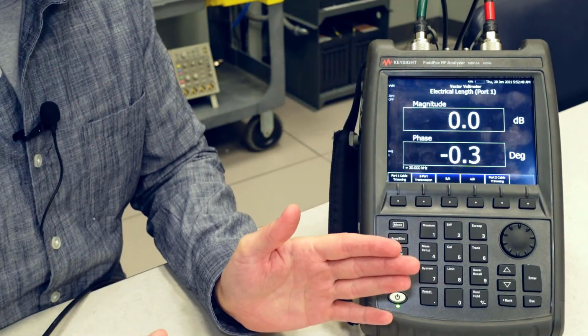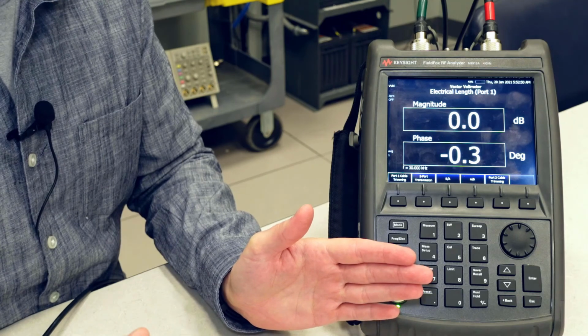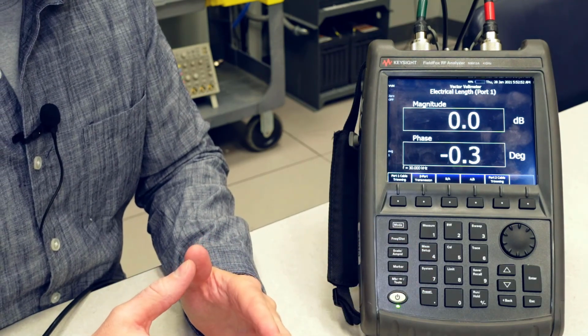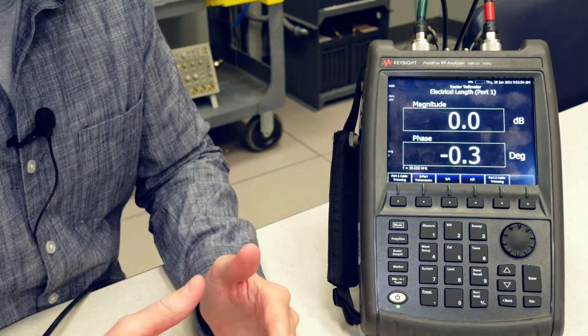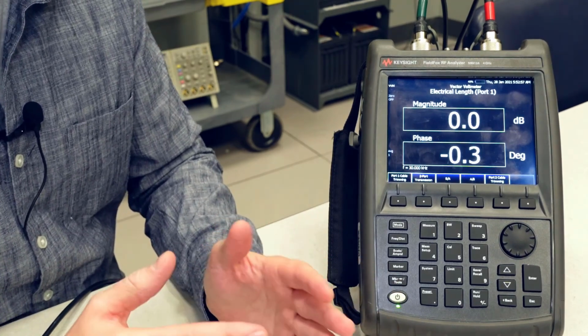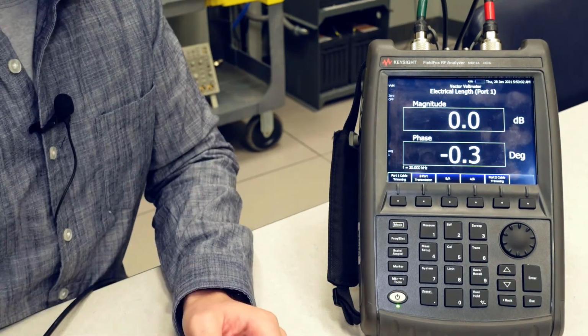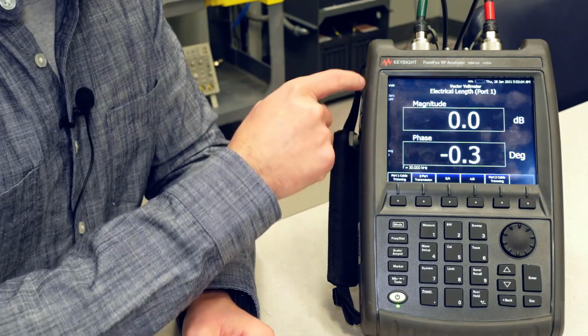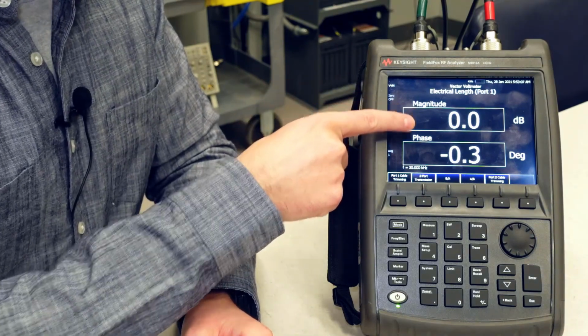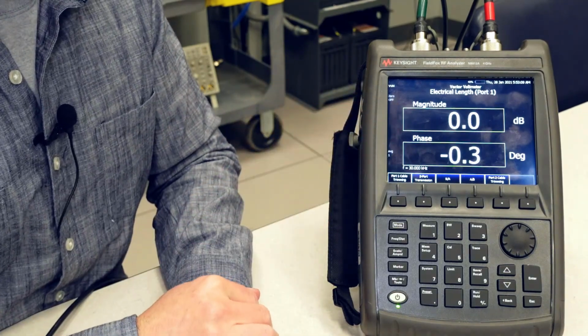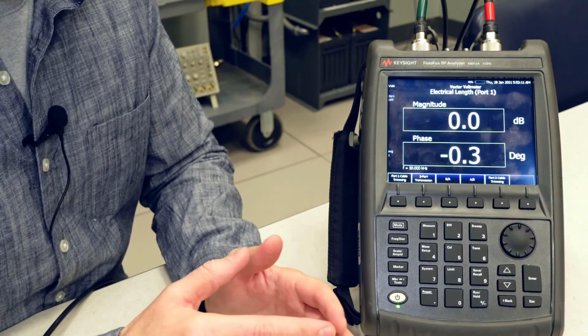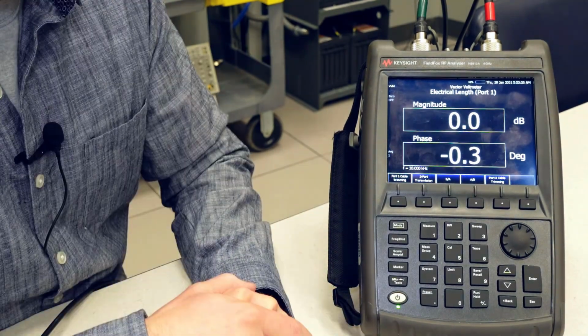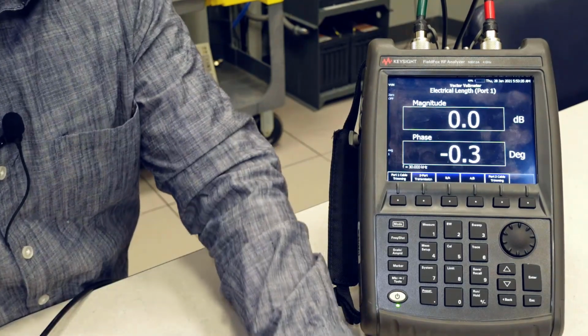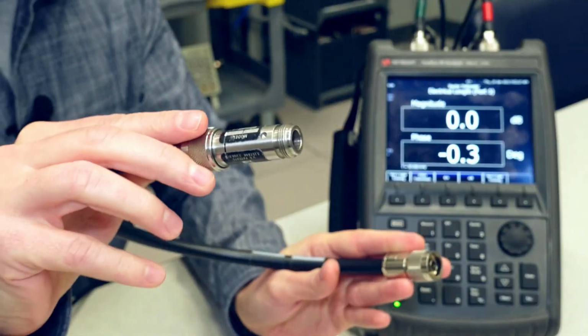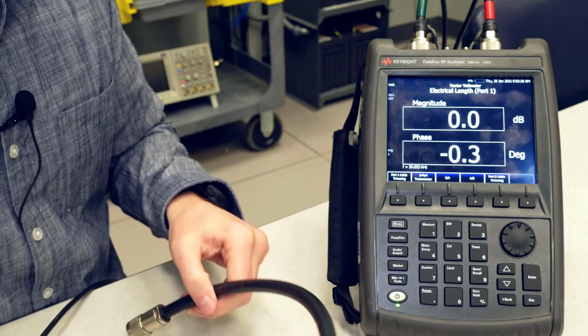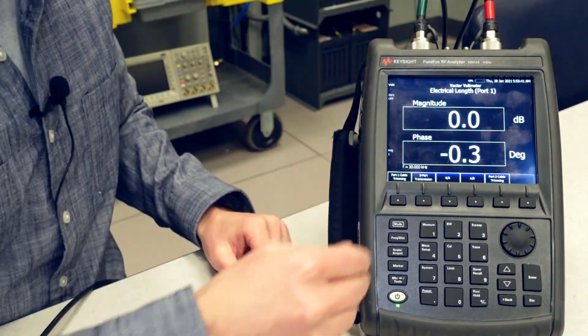You're not going to be able to tune anything with this, like a filter, or maybe see the response of an antenna at a range of frequencies. It's just designed for one frequency. But it shows it very simplistically with magnitude up here and your phase down here, and you'll be amazed at how quick the setup is compared to the network analyzer. And just to demonstrate that, I'm going to test the cable and attenuator just like I did for the network analyzer mode, but on the Vector Voltmeter mode here.